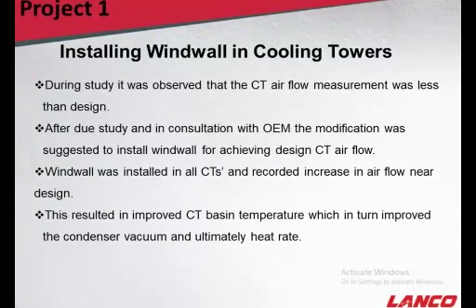So the idea was first how to achieve this. The wind wall was installed on one CT fan first, and the actual flow was measured. The impact was encouraging. So we multiplied this across all the CT fans thereafter. It was a costly affair at that time, but the result was improved CT basin temperature, which in turn improved our condenser vacuum and ultimately the heat rate.